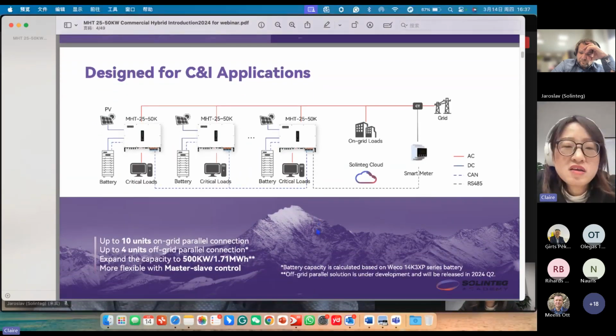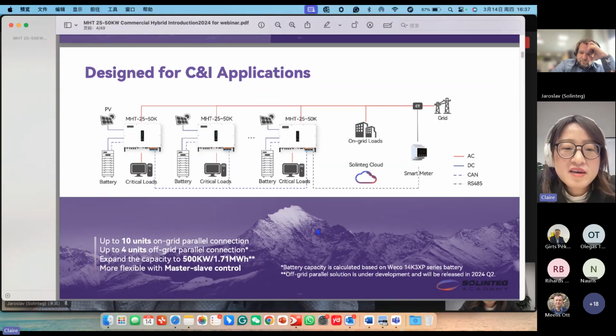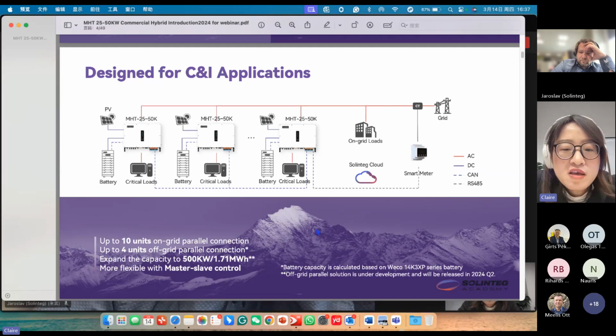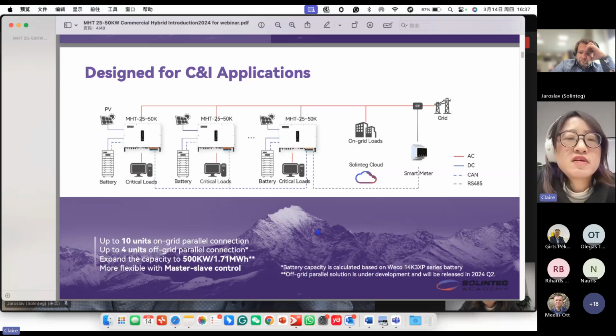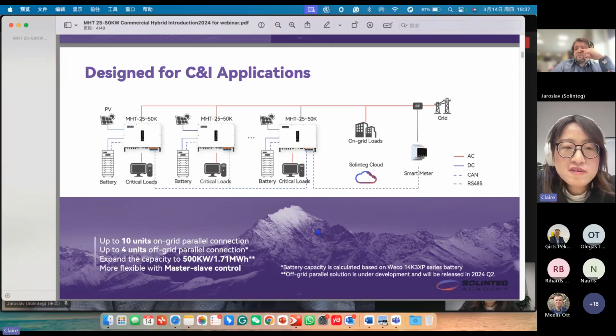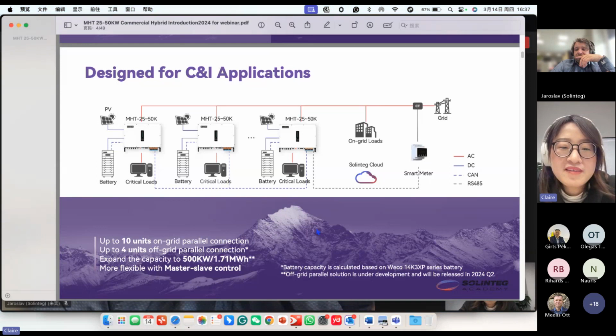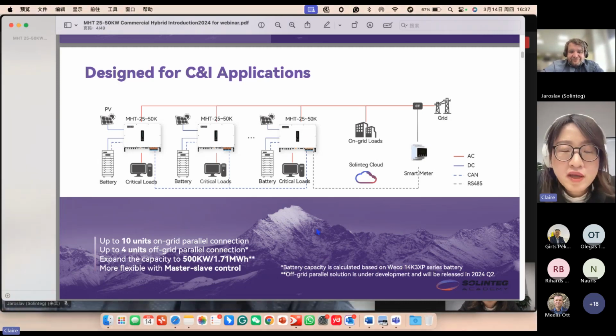And here is the application of the paralleling connection. It's on-grid paralleling connection. Currently, we support up to 10 pieces in parallel, which can extend our system from 25 kilowatts to 500 kilowatts, so our inverter can be used in bigger residential, small commercial, or even industrial applications. We also support 4 pieces off-grid parallel connection now, and in the near future, we will extend the off-grid parallel connection up to 10 pieces. This function can be realized at the end of Q2, so around the end of June.